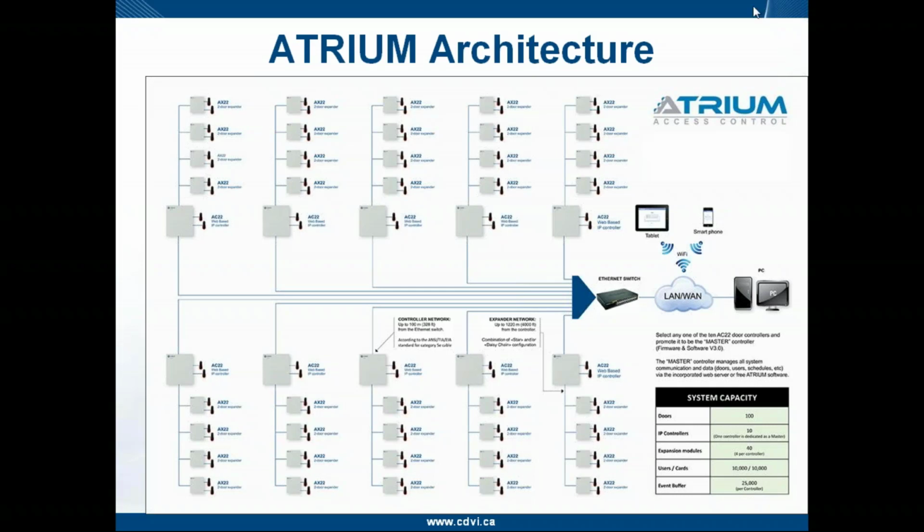So with that said, now this card has been granted or denied access. If it's been granted access at that door expander, on each reader port, the door expander will keep a temporary database, if you will, or temporary copy of the card number. And I'll explain why this is done. So for each reader on the expander, for each card that has been granted access at reader 1, we will store up to 500 card numbers in the expander's minuscule database.